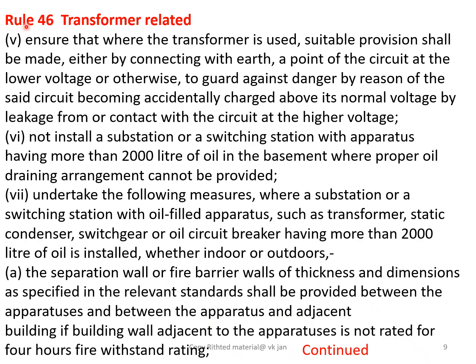Friends, we are now learning rule number 46 of CEA Safety Regulation 2023, which is related to transformers. Only a few of them are given here. First, ensure that where the transformer is used, suitable provisions shall be made, either by connecting with earth a point of the circuit at the lower voltage or otherwise, to guard against danger by reason of the said circuit becoming accidentally charged above its normal voltage by leakage from or contact with the circuit at the higher voltage.